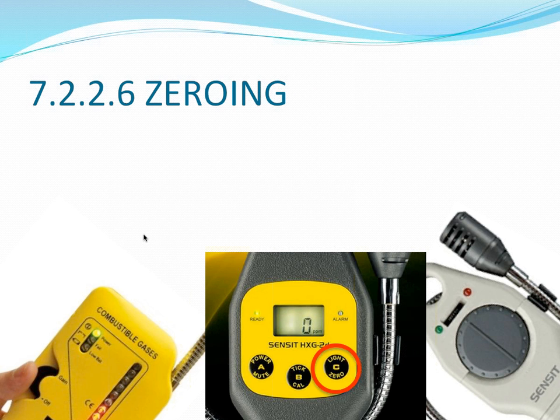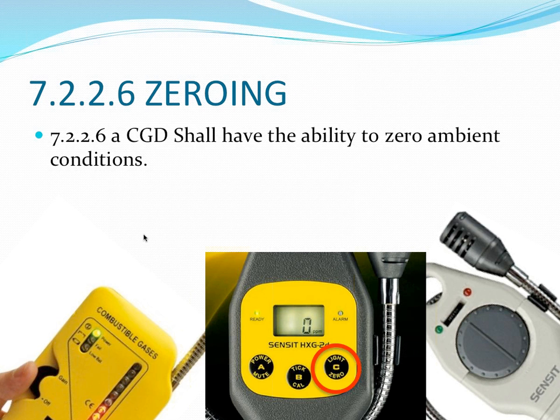Zeroing, that's another part of the standard, 7.2.2.6, zeroing of the combustible gas detector. They're looking for the product to be able to zero out ambient conditions. The reason for that is you're looking for a change in concentration. You're looking for the source of the concentration. So you want to be able to null out, or correct for, or ignore the current value as you move towards the higher value, the higher source.